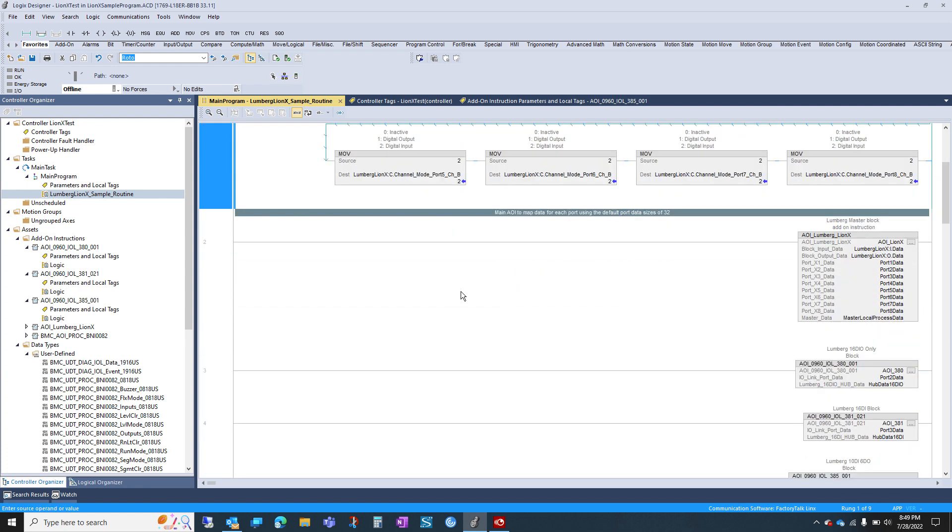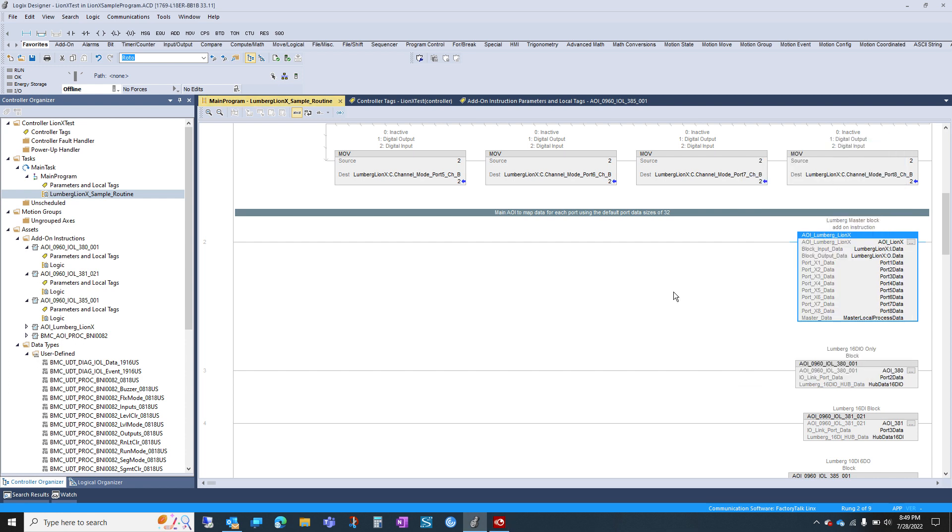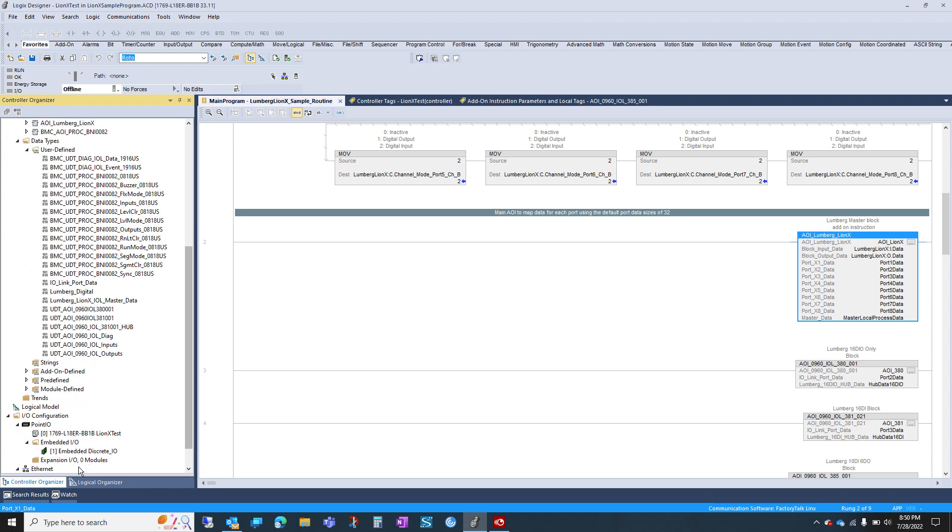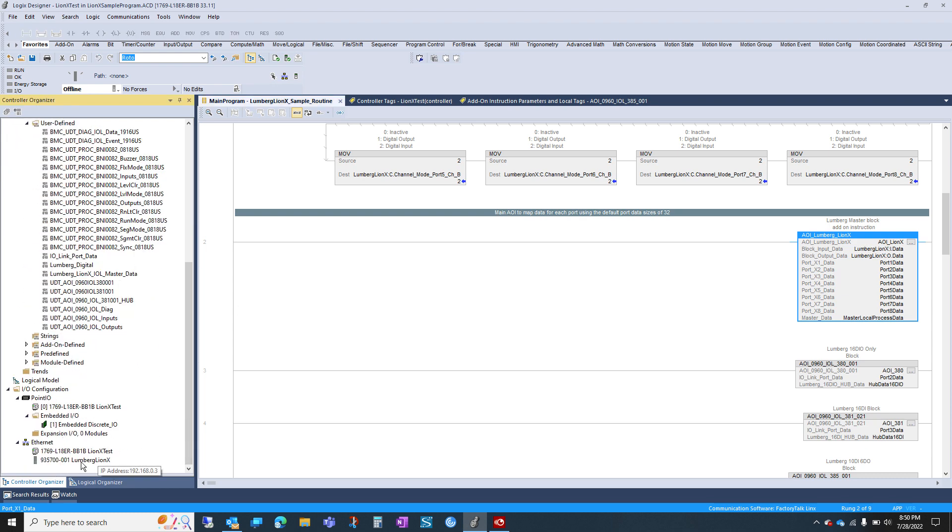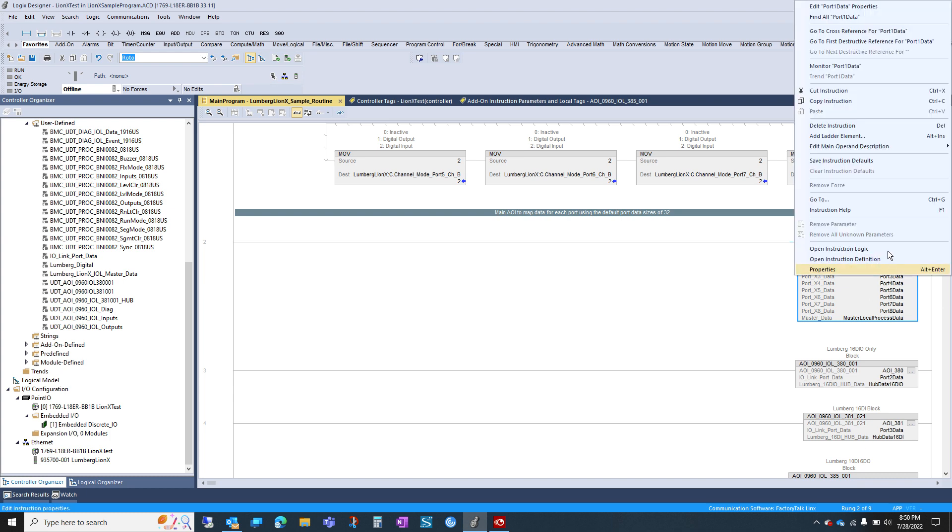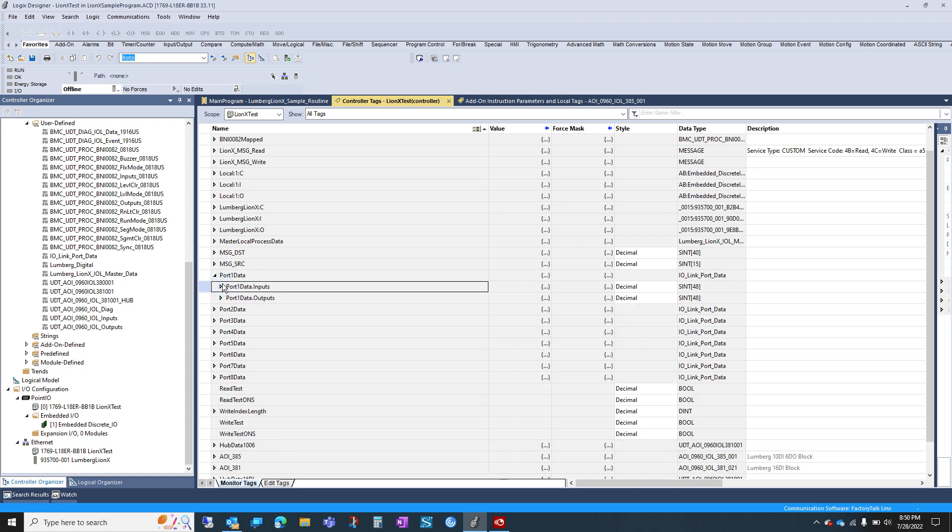Now here's a quick walkthrough for the AOI of the block. So here's the main AOI. The first one is just naming the AOI. This is the raw data of your Ethernet module itself. And then here is where your raw data is for each port. So if you plug an IO-Link device into it and you don't have an AOI, the raw data is going to be under that port. So port 1 is going to have all your input raw data and output raw data of that device.